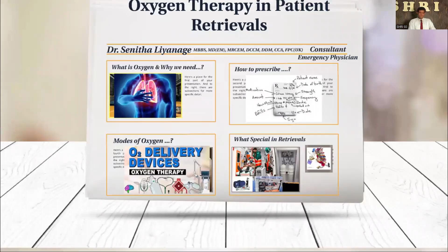Then, what are the specials on patient retrievals? How do we get the oxygen? So for oxygen, we have different ways. It is commercially produced by 2 oxygen companies in the country, and also there are 28 PSA plants in different hospitals. That is how oxygen is collected into our system. And there are domestic oxygen concentrators as well. We can get roughly 5 liters per minute or 10 liters per minute oxygen flow from domestic oxygen concentrators. But the purity is not 99% or 95%, the purity is less, but still it is effective.